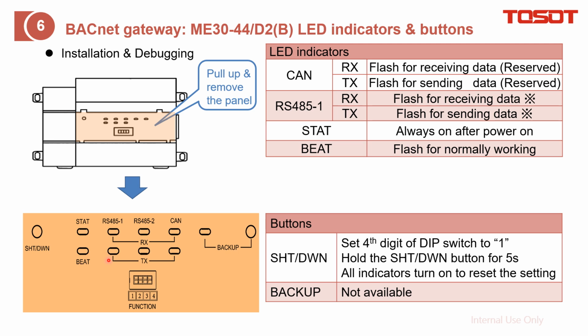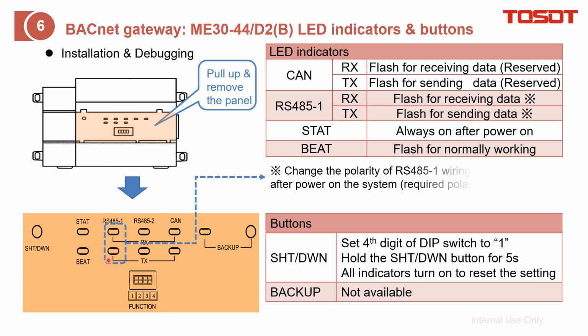This time we just apply this RS485-1, and on the wiring you need to check whether it is correct or not. If it is not, that means the polarity is not correct; you need to change A and B, that's fine.